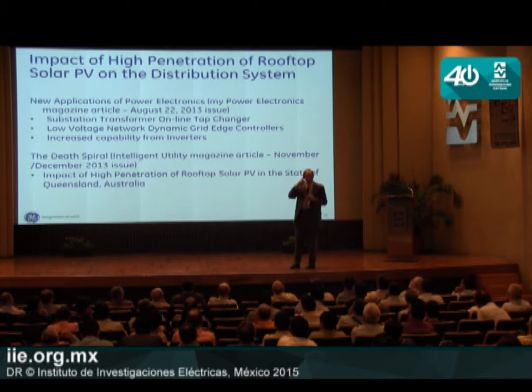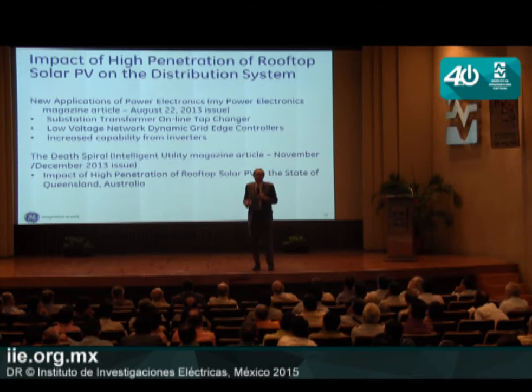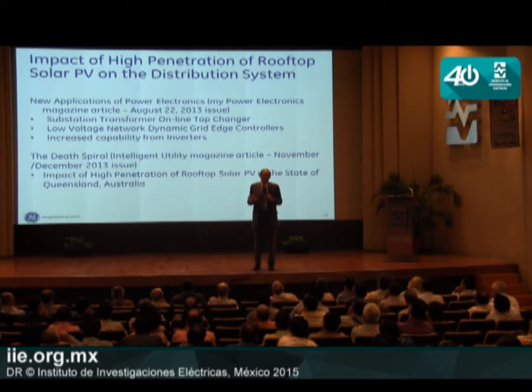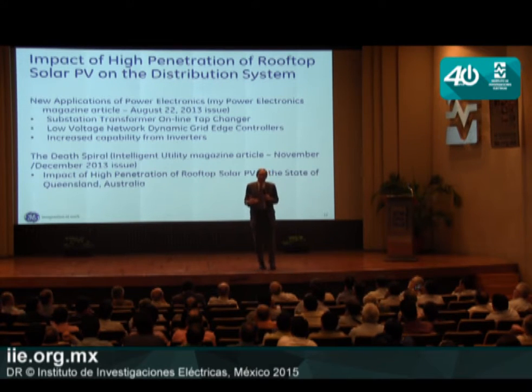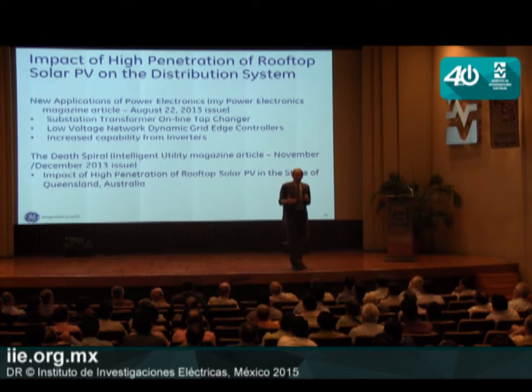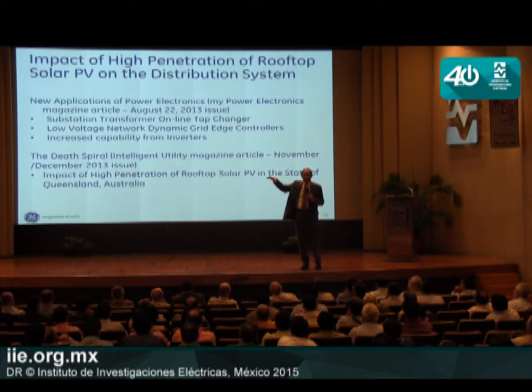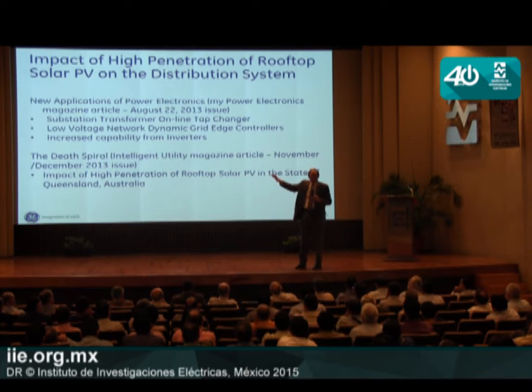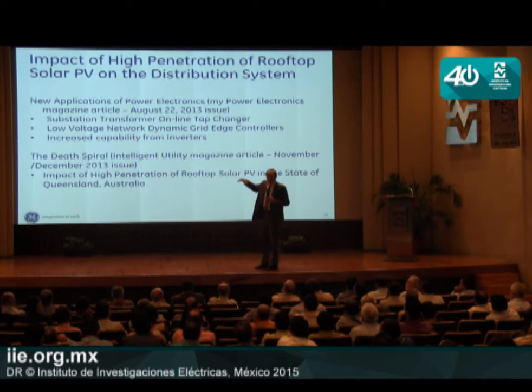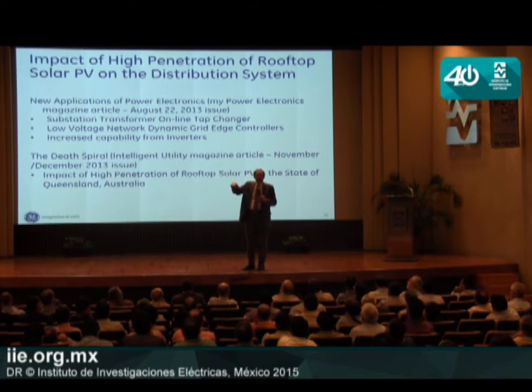Now with 35% penetration of rooftop solar PV on that feeder, the tap changer is operating 90 to 100 times per day instead of 5, and its lifetime is now well less than 5 years. So the takeaway is: mechanical means of control for the grid of the future, with high impact of renewables, just aren't feasible. They don't make sense. So we, and our competitors, now have a power electronics-based tap changer.